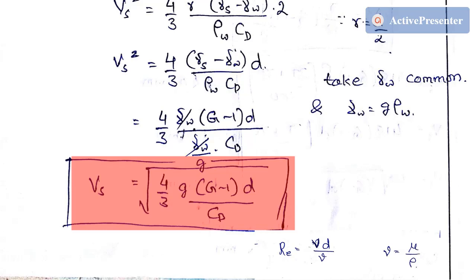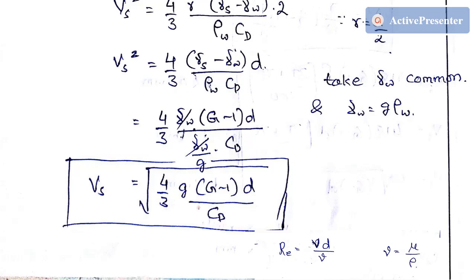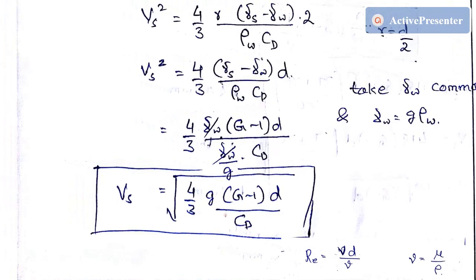The settling velocity equation is: Vs = √[4/3 × g(G − 1) × d / Cd]. The parameters in SI units are: velocity in m/s, g in m/s², G is dimensionless, d in meters. The drag coefficient Cd depends on the flow regime — laminar, turbulent, or transitional — which is determined by the Reynolds number.